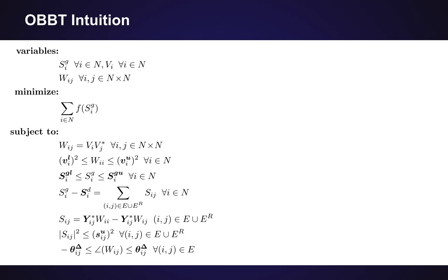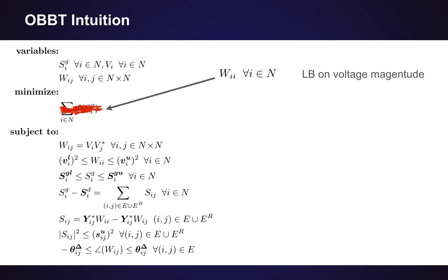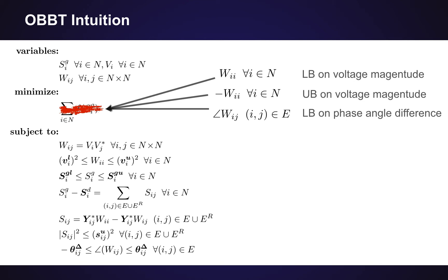What's the intuition of OBBT? This is our original AC power flow problem. We're going to ignore the original objective function, which minimizes cost, and replace it with different quantities of interest that will yield variable bounds. If we minimize W_ii, at the globally optimal solution we'll get a lower bound on the voltage magnitude. If we negate it, turning minimization into maximization, at the global optimal solution we'll get an upper bound. We can do the same trick for the angle of the W_ij variables, telling us how wide the angle difference can get on any branch in the network.